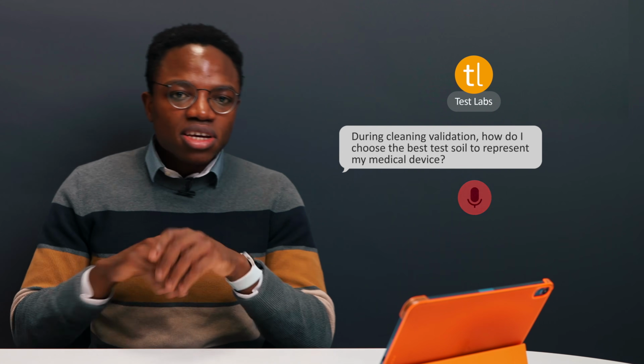And the next question now is very specific to cleaning validation, and that is, during cleaning validation, how do I choose the best test soil to represent my medical device? Good question. So there is guidance in 2 to 3 specific places. 15883-5, TIR 12, ST98, as well as some supplementary standards for test soils and test soil justification.